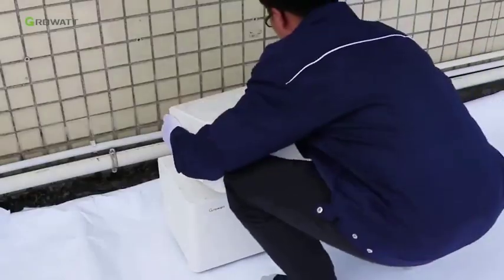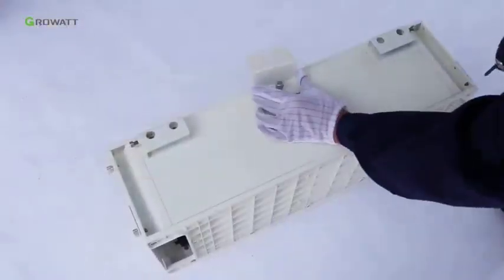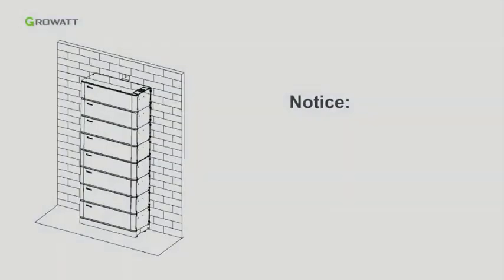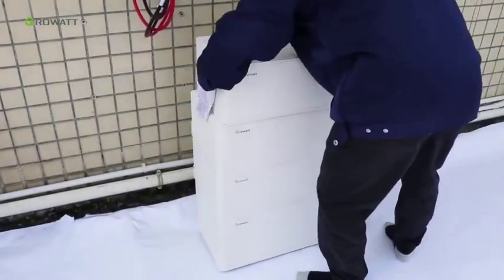Stack the second and third ARK battery pack. Install the safety part in the final ARK battery pack. Note: the safety part needs to be installed at the top battery. However, once the number of battery packs is higher than seven, one more safety part should be installed in the middle battery. Stack the final battery pack.